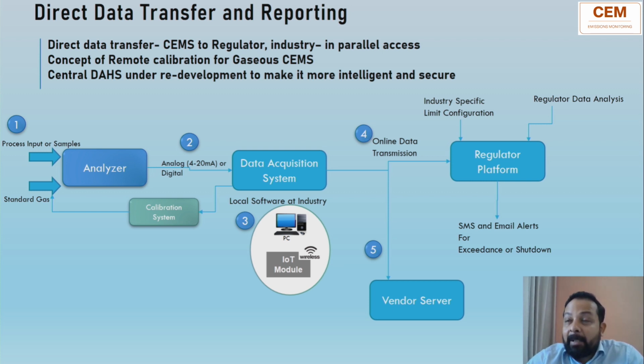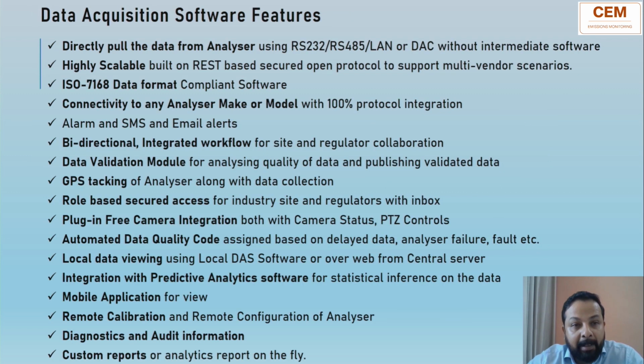If regulators see inconsistency in the data for a longer time and are planning to check the installation, they can check it remotely for gaseous CEMS, called remote calibration or remote check, possible mostly in India. Under that, the data acquisition system already has a command inbuilt system where they can click the zero drift and span drift check online. This calibration triggers the instruction to the analyzer directly to get the zero gas, report the measurement, and then the span gas and report the measurement. It gives the regulator confidence in how the gaseous CEMS installation on site is responding. This is one of the unique systems in the Indian data handling system for CEMS.